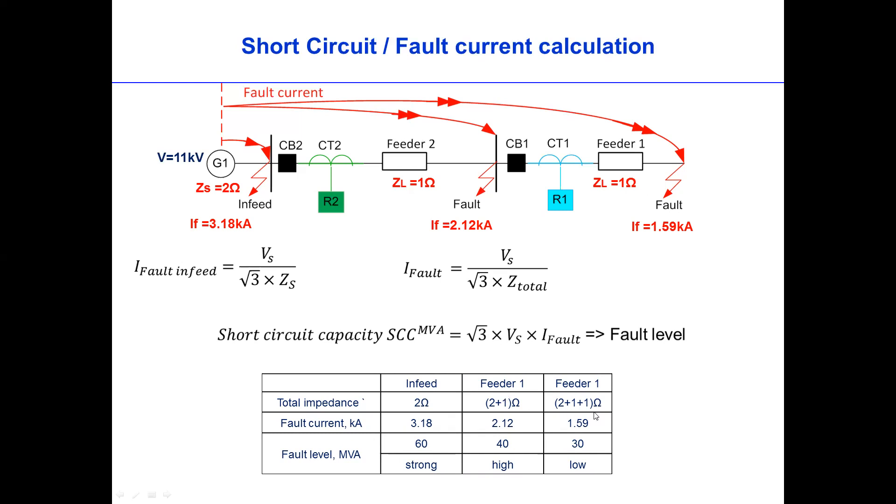And at feeder one here, it is 1.59. In terms of fault level, if we just use this formula, then this will be 60 MVA on the generator one or on the infeed, then 40 MVA on this one, then 30 MVA on here. What it tells is, the fault near the source or the infeed is strong, while the fault far from the source is low or weak.